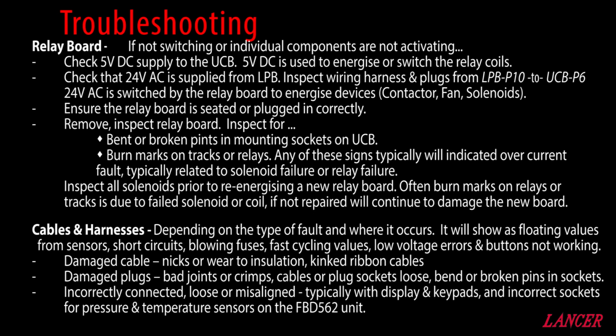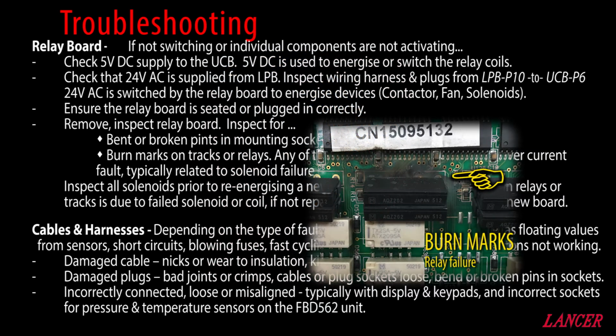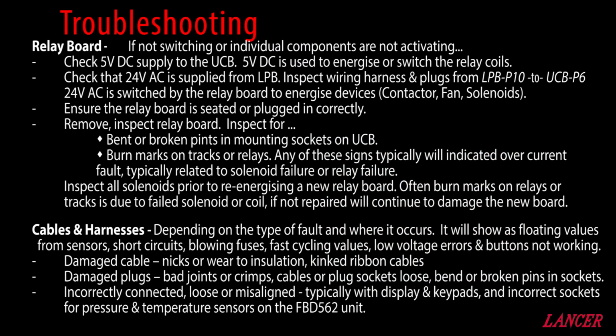Check that the 24V AC is supplied from the lower power board, and ensure that the relay board is seated or plugged in correctly. Remove and inspect the board. Inspect for broken or bent pins, burn marks on tracks or relays. It is very important that if we see these burn marks, that we inspect all solenoids and coils prior to re-energizing the new board, as this fault will reoccur again if it's due to a failed solenoid or coil.